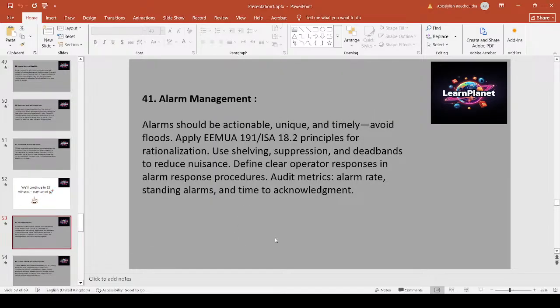Topic 41, alarm management. Alarms should be actionable, unique, and timely. Avoid floods. Apply EEMUA 191 and ISA 18.2 principles for rationalization. Use shelving, suppression, and deadbands to reduce nuisance alarms. Define clear operator responses in alarm response procedures. Audit metrics: alarm rates, standing alarms, and time to acknowledgement.